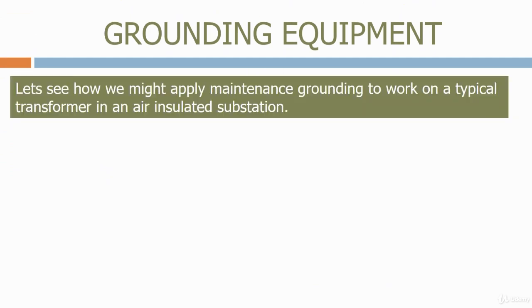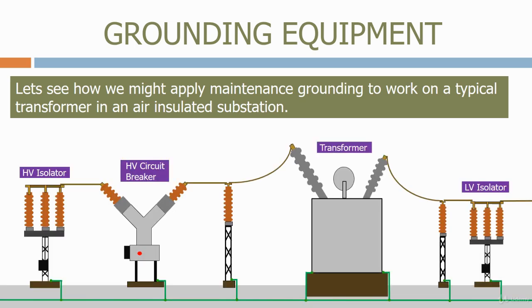Let's see how we might apply maintenance grounding to work on a typical transformer in an air-insulated substation. Here's a typical transformer circuit with an isolator and circuit breaker on the high voltage side and an isolator on the low voltage side. The first stage in this process is to electrically isolate the equipment we intend to work on. To do this, we open the circuit breaker and then open the isolators on both sides of the transformer.